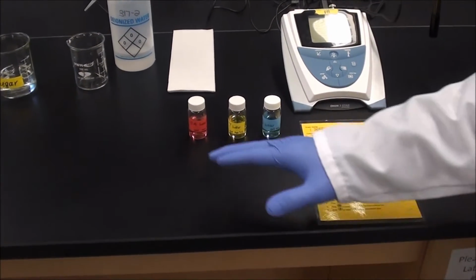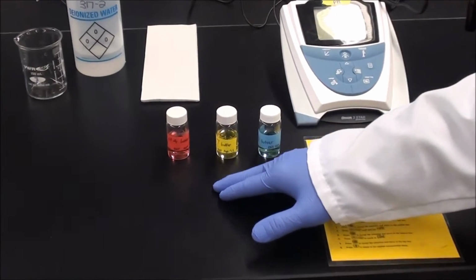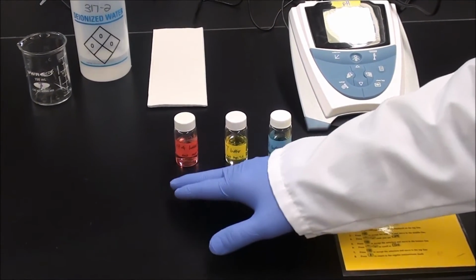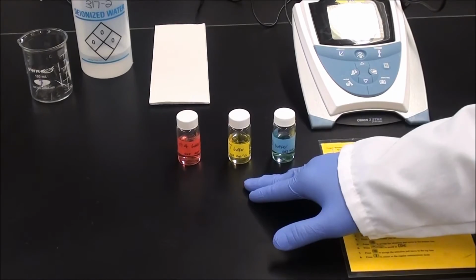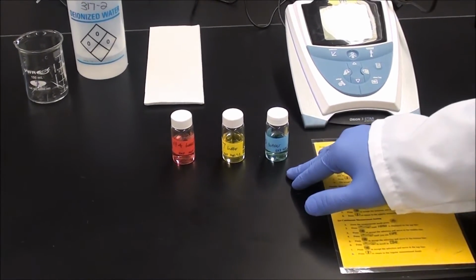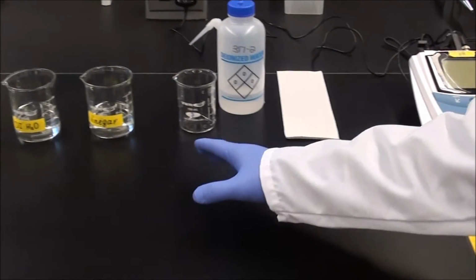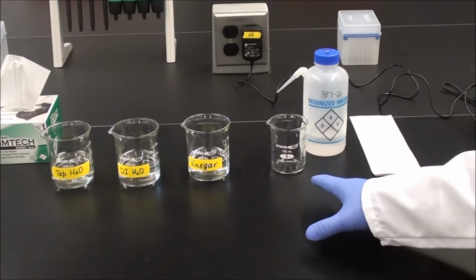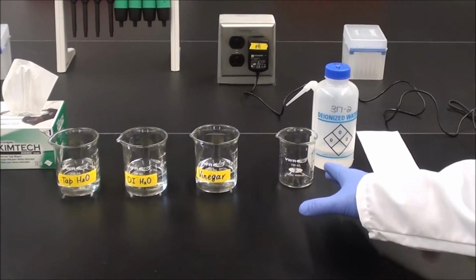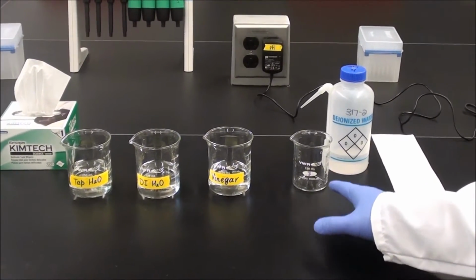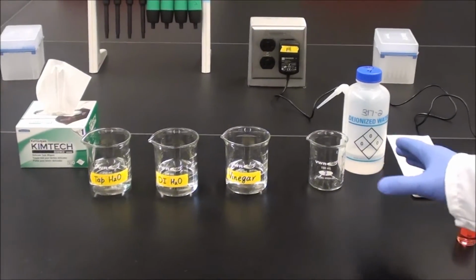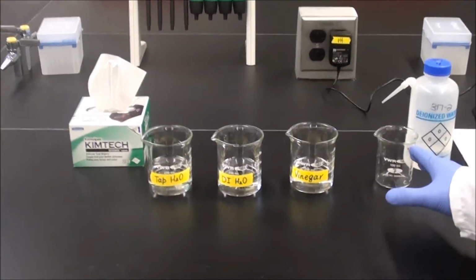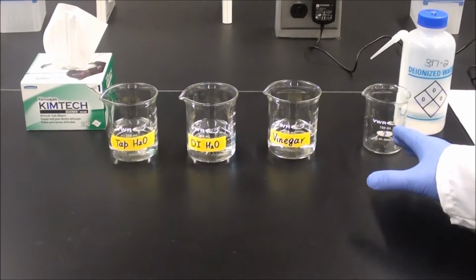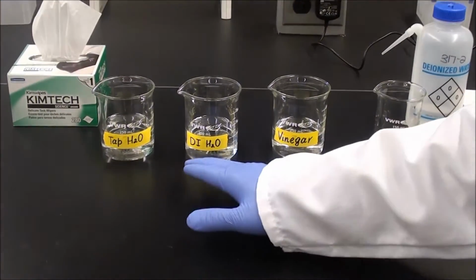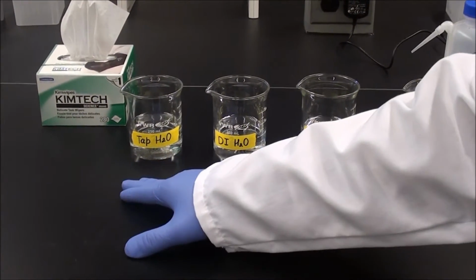We're going to need 3 colored buffers with fixed pH: pH of 4, pH of 7, and pH of 10. We're going to need a beaker and deionized water in order to rinse our pH probe every time that we use the buffers. And the 3 solutions that I will be measuring the pH of are vinegar, DI water, and tap water.